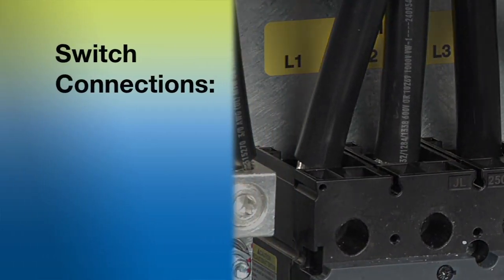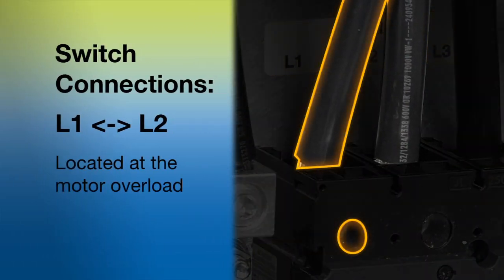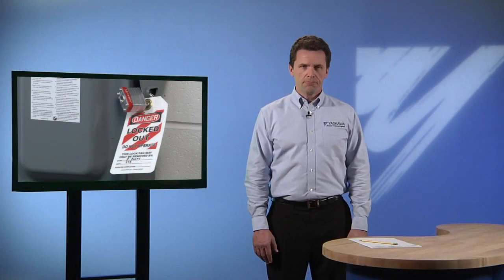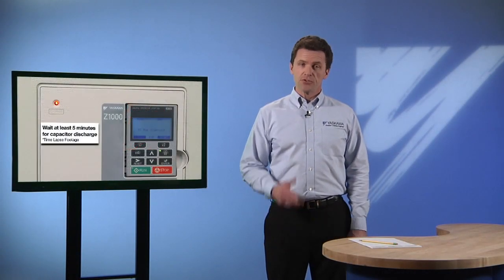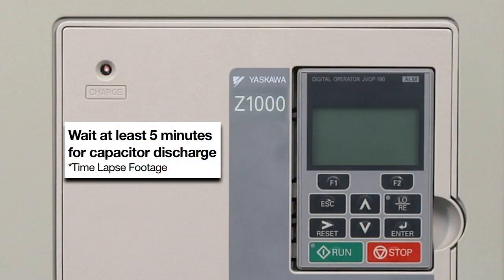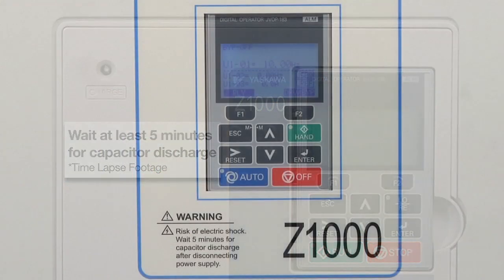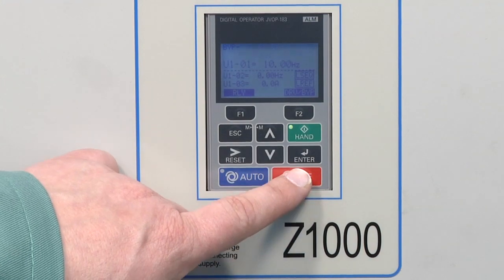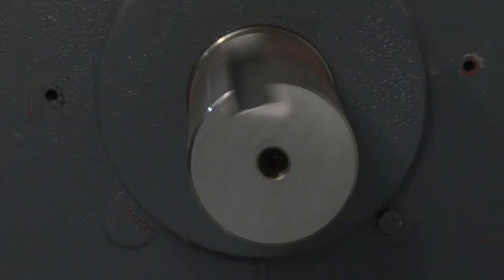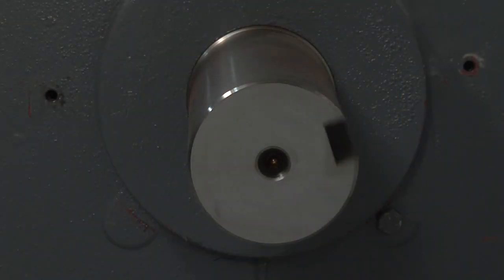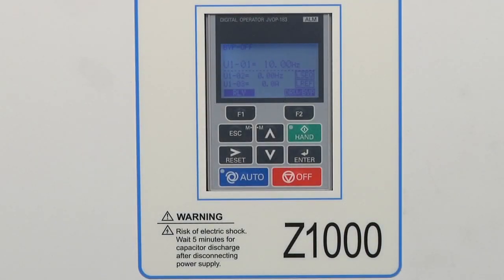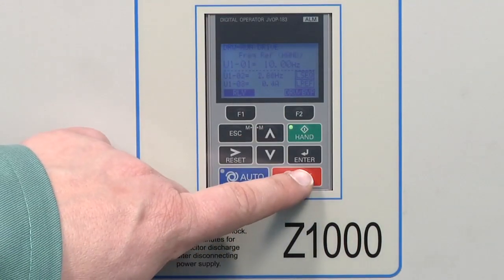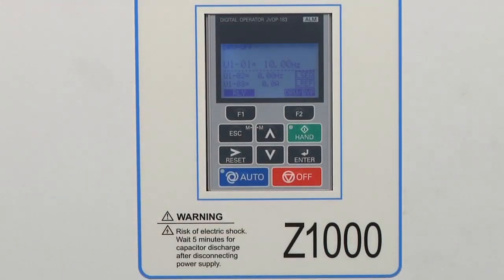If the rotation isn't correct, switch connections L1 and L2 at the top of the circuit breaker. Remember to power down, lock out, and wait 5 minutes just as we did when we switched the motor output at T1 and T2. Perform the bumping procedure once again, hand, then off. And when you check it now, the motor should be spinning in the proper direction. Once the connections are switched, press the F2 key again to return the bypass to drive mode. Do a final bump to confirm that the motor is still rotating in the proper direction in drive.